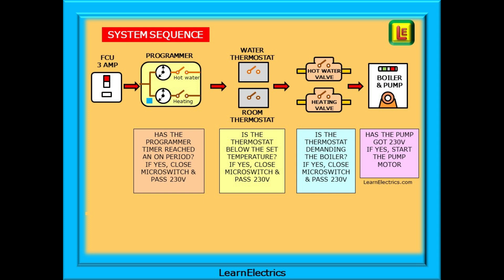If the thermostat is demanding the boiler, the microswitch in the valve closes and passes 230 volts to the pump motor. And finally, has the pump motor got 230 volts? Yes, it has. So start the pump. It is just a series of questions to which the answer to every question must be yes before the pump will start.